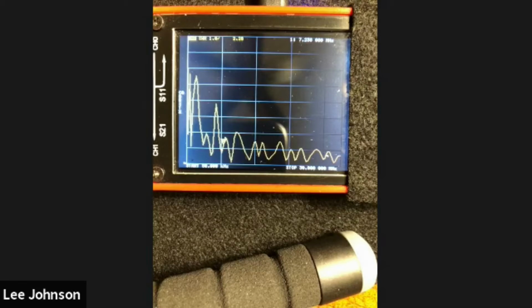On some of the newer firmware packages on the nano VNAs, you can actually ask the marker to go to the minimum SWR point, and it'll go there. You don't have to move it with a pointer. Then you can adjust the traces as you see fit to tweak up whatever measurements you want. But that notion of starting with defining the traces, putting the stimulus in, and making sure your calibration has either already been done, or set up and do it, because let's say you're measuring your walkie-talkie antenna at 2 meters and 70 centimeters, and you're set for a 50 kilohertz to 30 megahertz scale. Well, you're going to have to recalibrate.